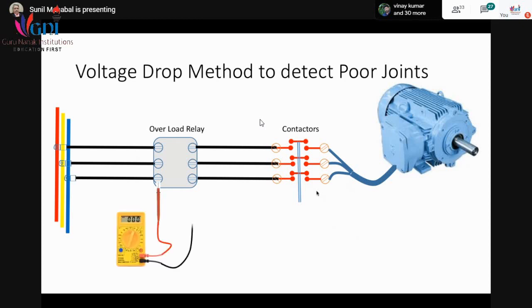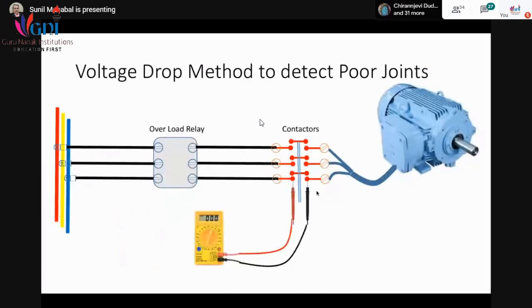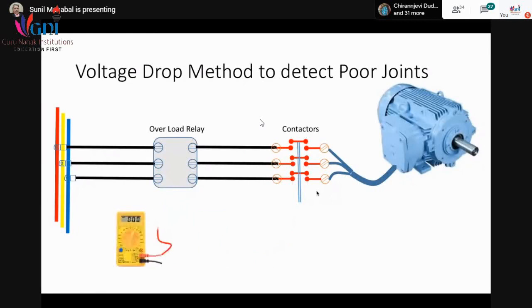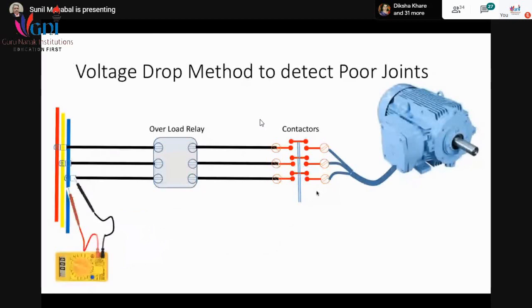Then I checked whether there is voltage drop across the same phase of the overload relay. And I did this in all three phases. I have demonstrated only a single phase here, but I did it for RYB. And then finally I reached the bus bar and the lug of the cable. There I got the voltage drop. I never expected that the voltage drop would happen there. I thought it would be in the contacts of the contactor. But I got a substantial voltage drop in the lug and the bus bar.